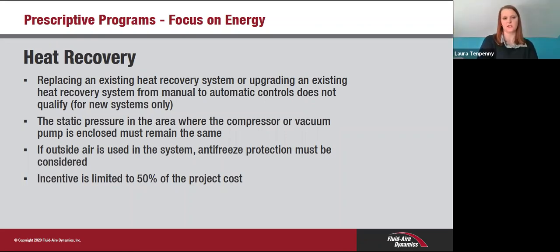Yeah, and it will make a difference too. Are you in a shop where you have air conditioning, and you know you're going to be saving on that air conditioning side of it? If you're dumping the heat outside in the summer and keeping it on the inside in the winter as well, we do have that prescriptive route if it fits that. But if you have a specific situation where it doesn't, we can always look at things as a custom project. And we've done this on things other than just air compressors, if you're recovering heat off of a chiller or something like that too.